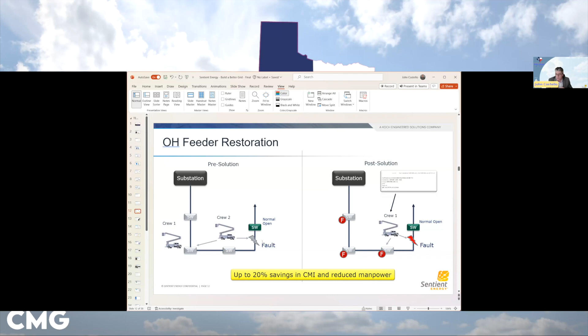But essentially, depending on how many sensors you put on the feeder, you can get more and more granular so that you know that a fault is within this specific span. We see most of our customers will either bifurcate the segment itself so that there's just 2 areas or perhaps 3 areas, but we've seen some go as many as 6 different segments on that circuit. So they've reduced their response time, and we take out the chance that you guessed right the first time. On average, you can reduce it 84%, and you can see a significant savings on average in CMI and in reduced manpower.